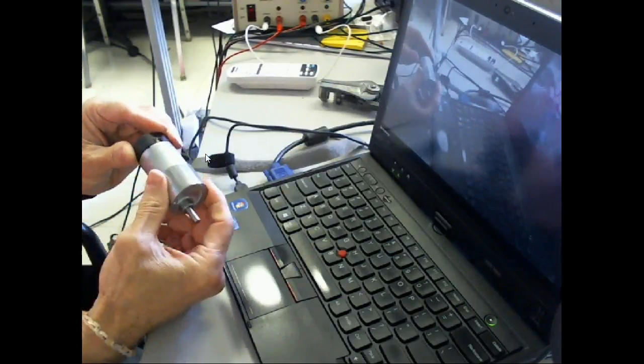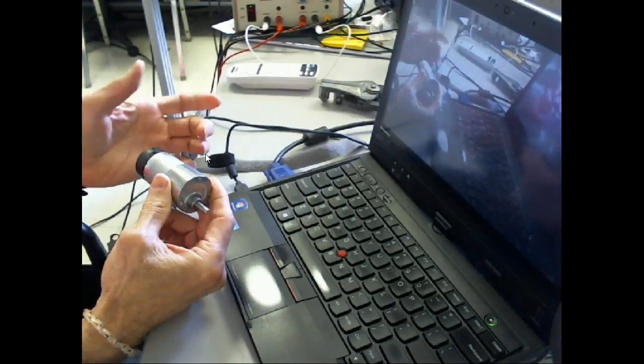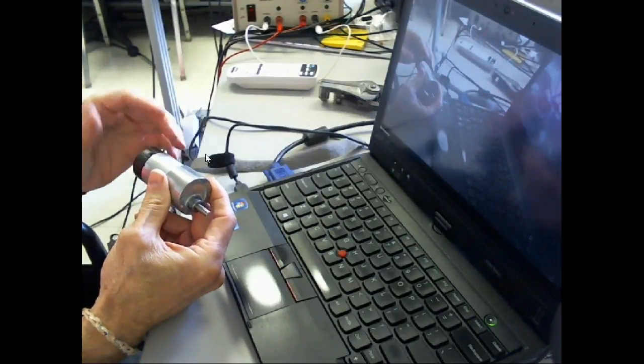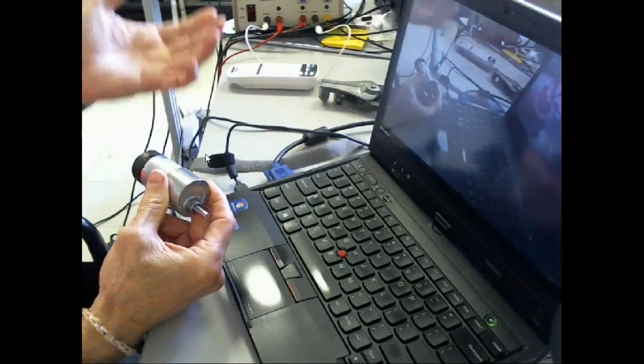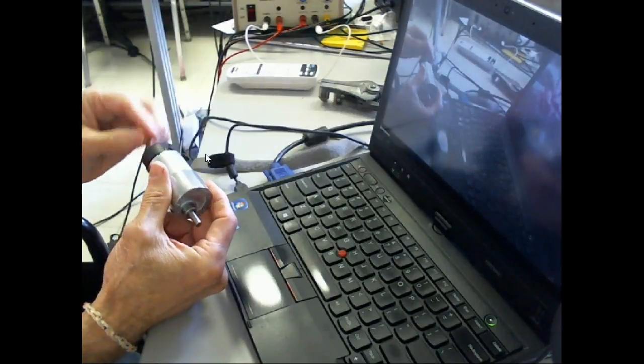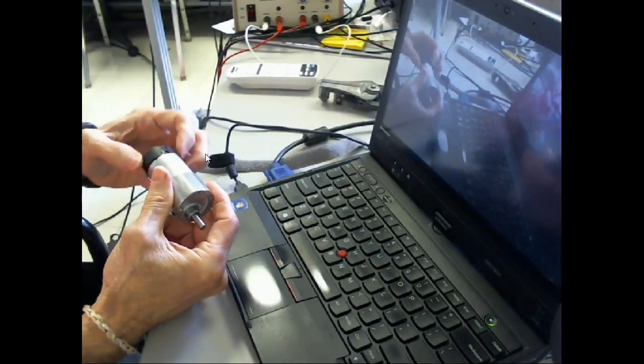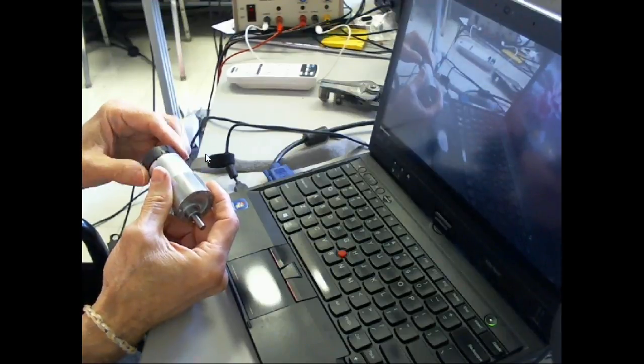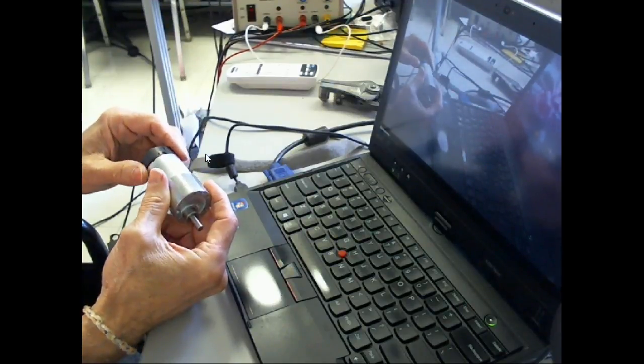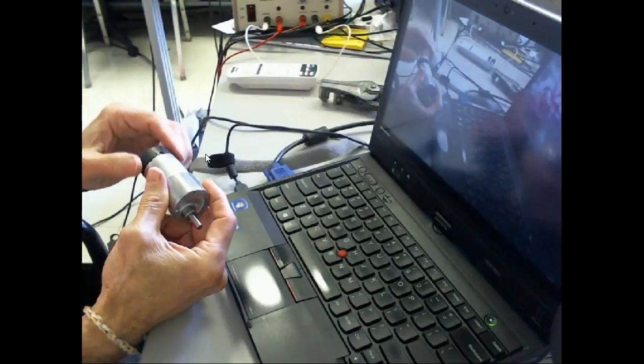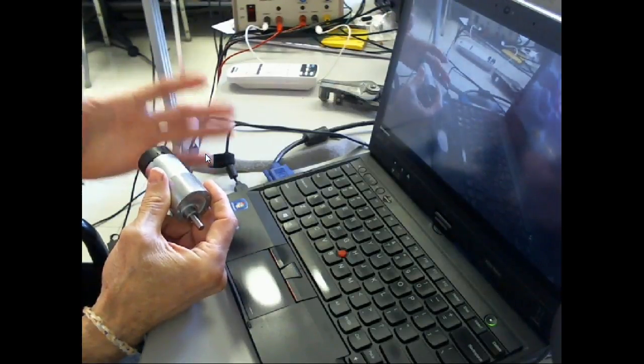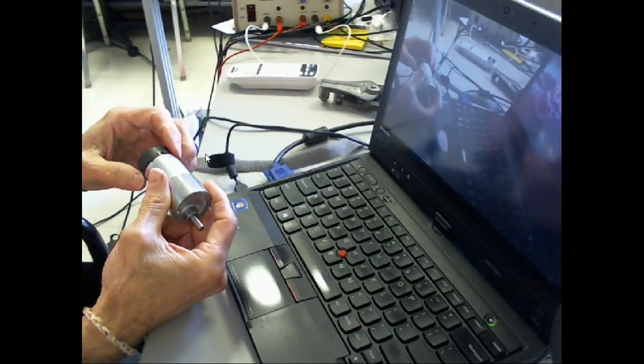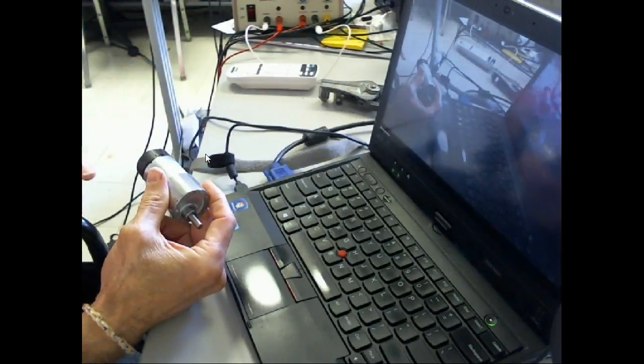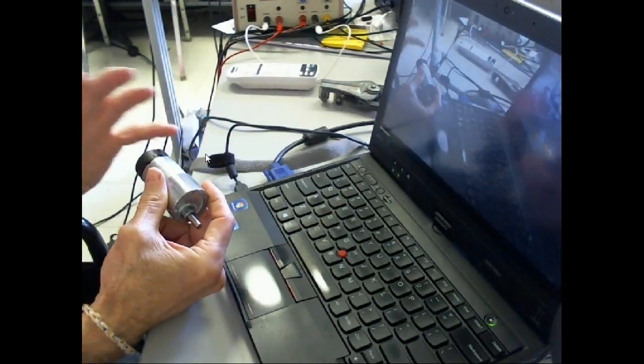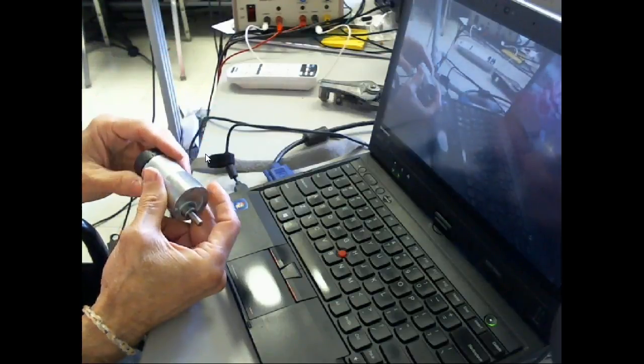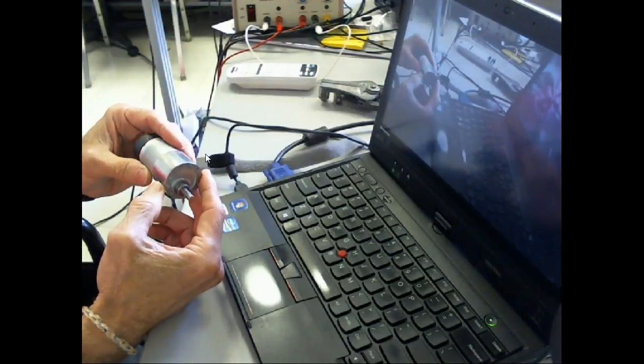Now the encoder gives us the pulses. If we count one pulse, let's say from rising edge to rising edge, then there's 32 pulses per revolution. But on a PLC, we can set it to count not only the rising edges but also the falling edges. If we count both, that would be 64 pulses per revolution. But let's use 32, that's what we've seen before.